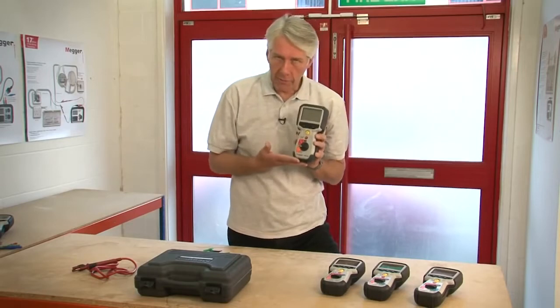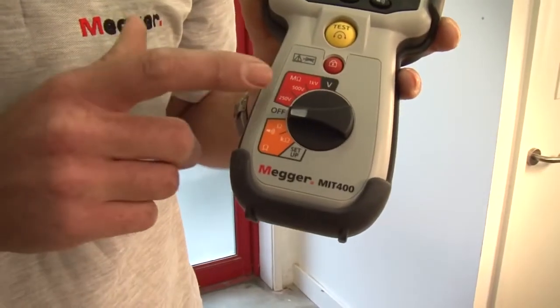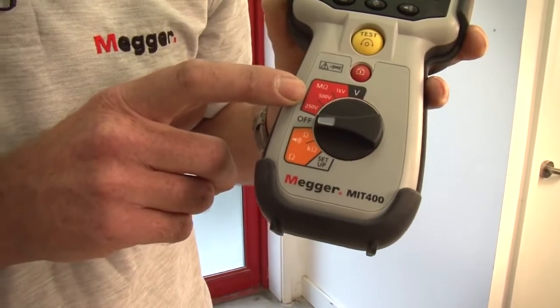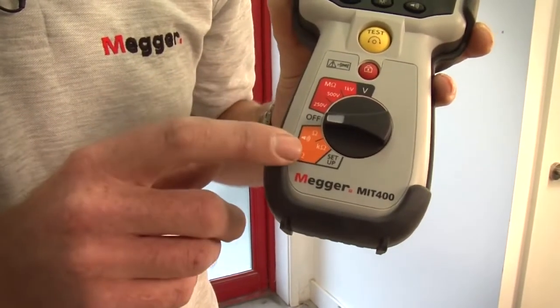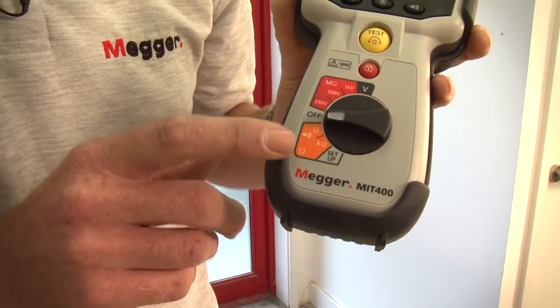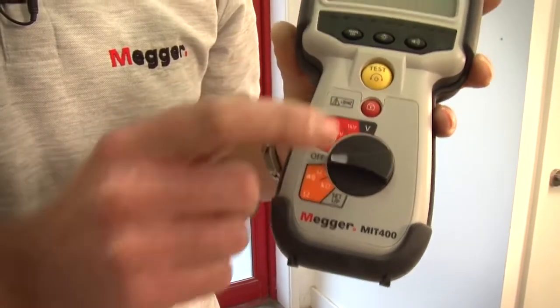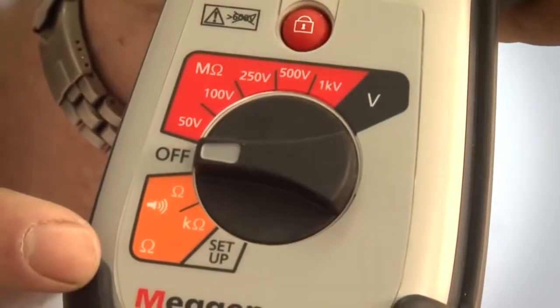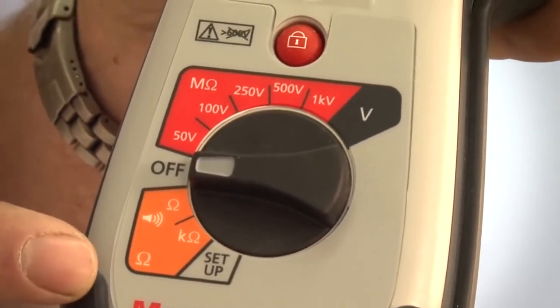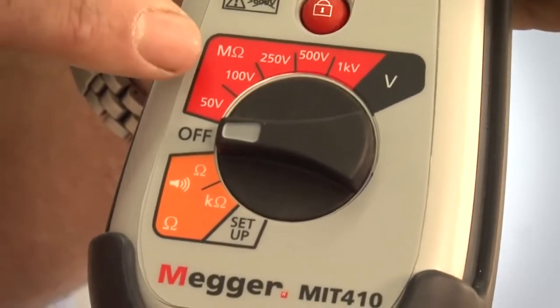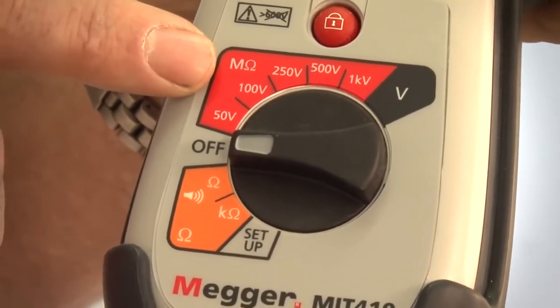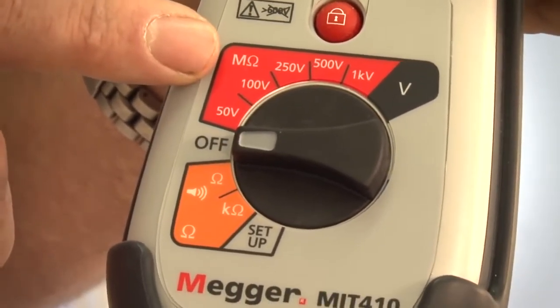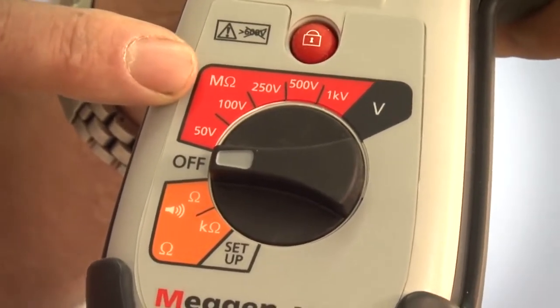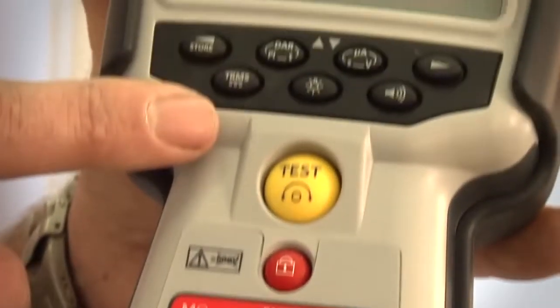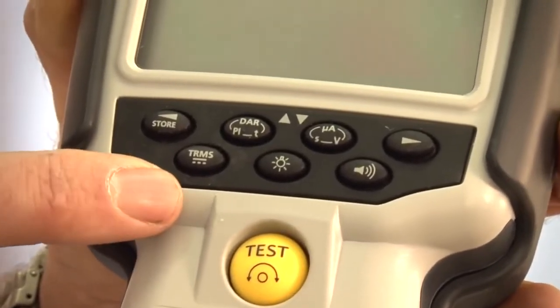Here we have the MIT400, which is the entry-level product. It has 250, 500 and 1000 volt insulation test ranges. It has a continuity range with a buzzer, a kilo ohms range and a voltage measuring range. The MIT410 has all of the ranges and features of the MIT400 with the addition of 50 and 100 volt insulation testing ranges and an increased measurement capability up to 100 gigohms. With this product, you can also perform polarization index ratio, dielectric absorption ratio and other time tests.